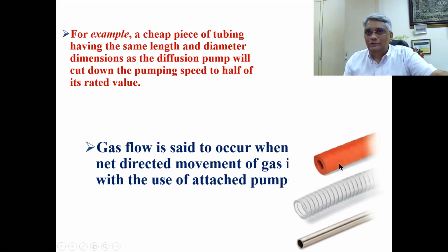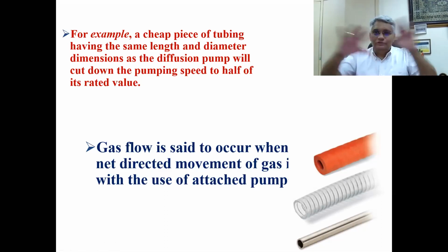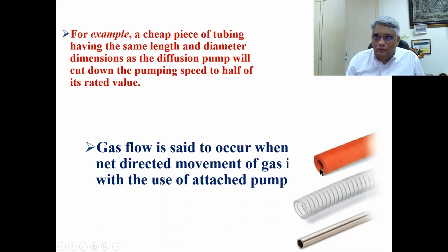The one shown on top is a typical rubber pipe, not desirable, because you're taking air molecules out, and the same thing happens here, because I'm using this pipe to pump air from one side to the other, the right side being the pump side and the left side the chamber side.